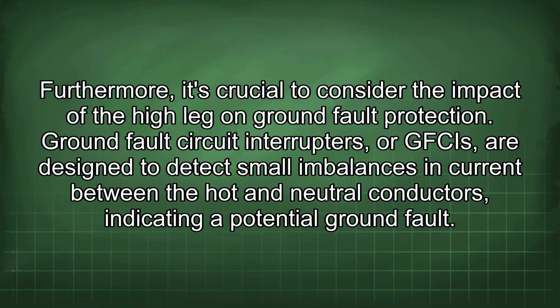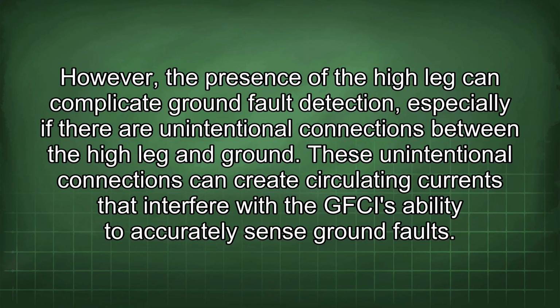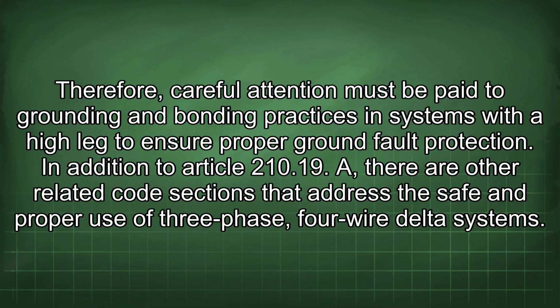Ground fault circuit interrupters, or GFCIs, are designed to detect small imbalances in current between the hot and neutral conductors, indicating a potential ground fault. However, the presence of the high leg can complicate ground fault detection, especially if there are unintentional connections between the high leg and ground. These unintentional connections can create circulating currents that interfere with the GFCI's ability to accurately sense ground faults. Therefore, careful attention must be paid to grounding and bonding practices in systems with a high leg to ensure proper ground fault protection.